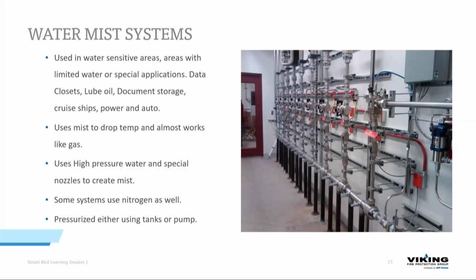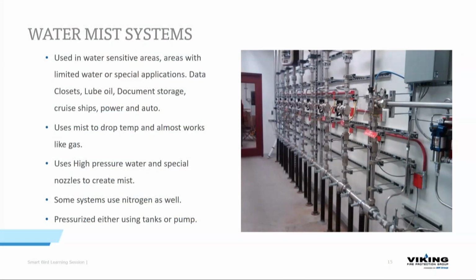Some of the other products that are in this lineup use nitrogen as well as a backup. They're pressurized either using tanks or pumps. You will notice that is a ton of pipe stands and a lot of unistrut. When we're talking about high pressure, we're talking about 5,000 PSI in some cases. So this stuff has to be buckled down tight. And that is one of the expenses. The hangers are one of the more expensive things that go into the installation of these types of systems.